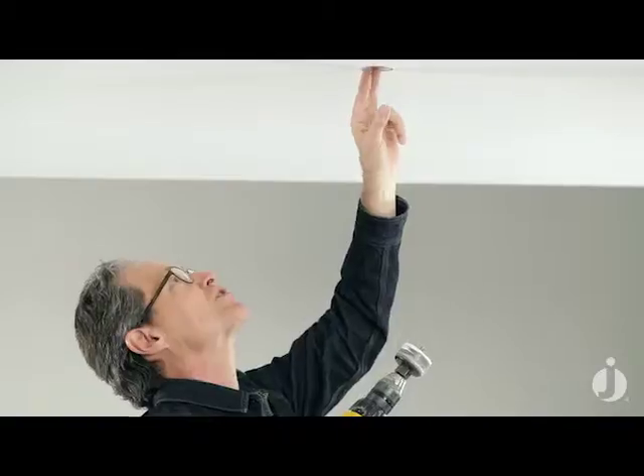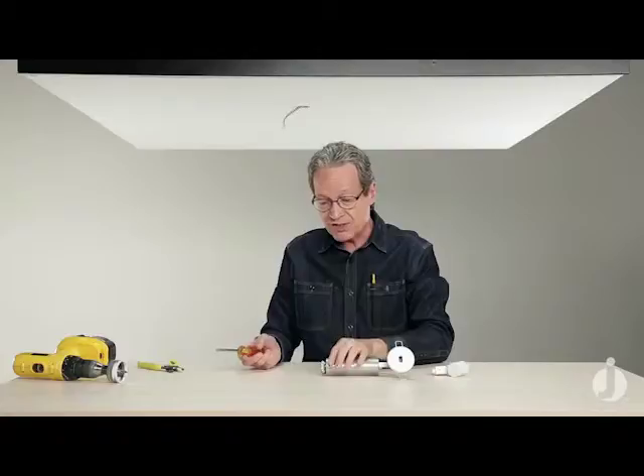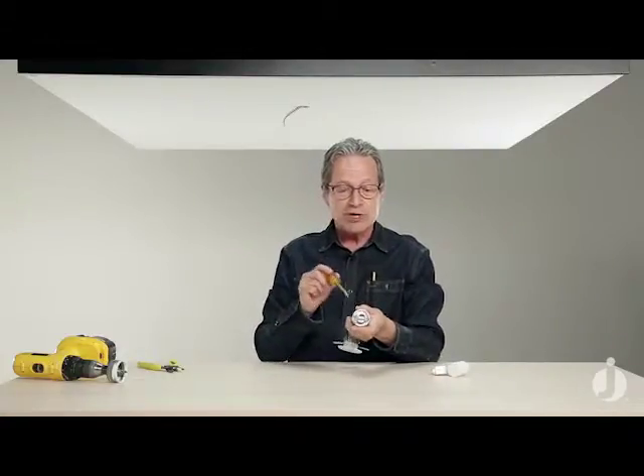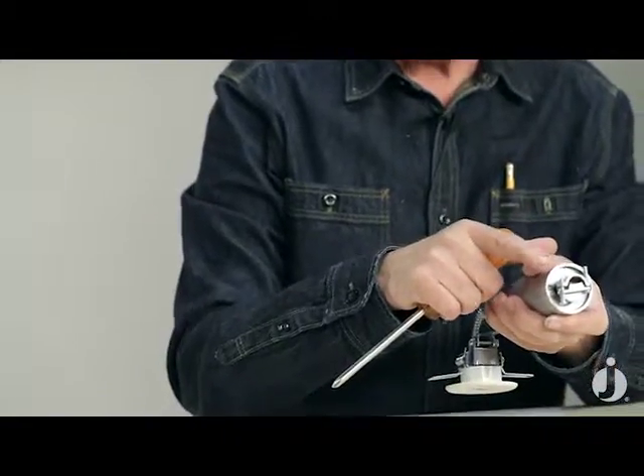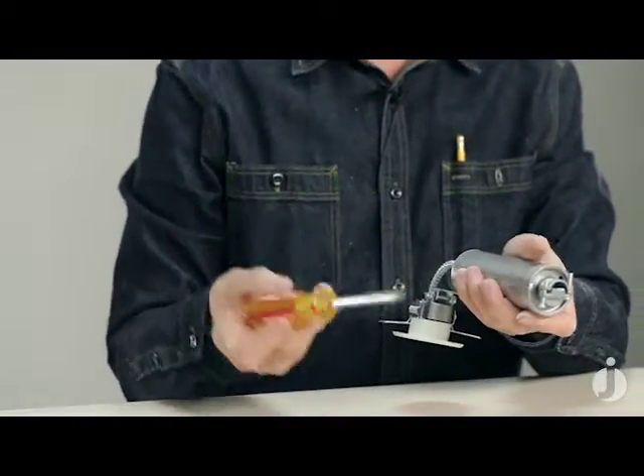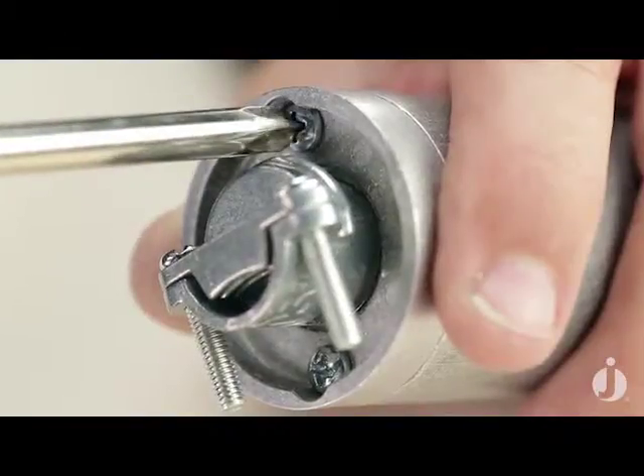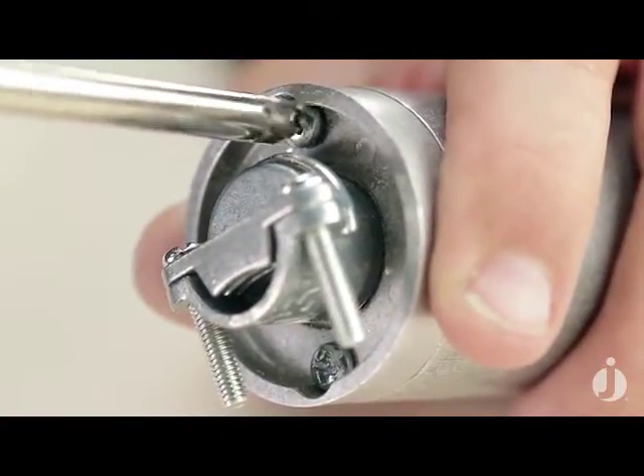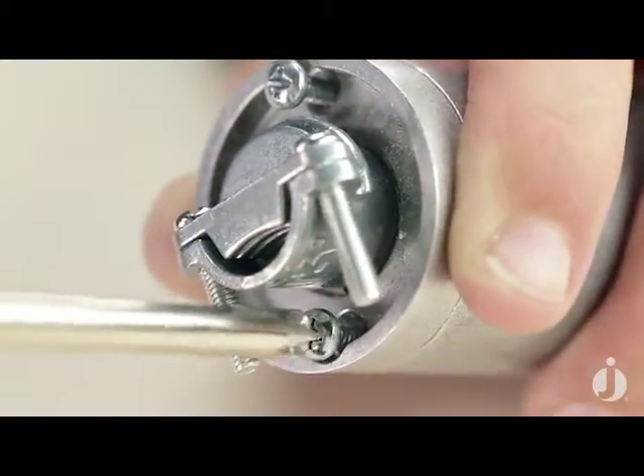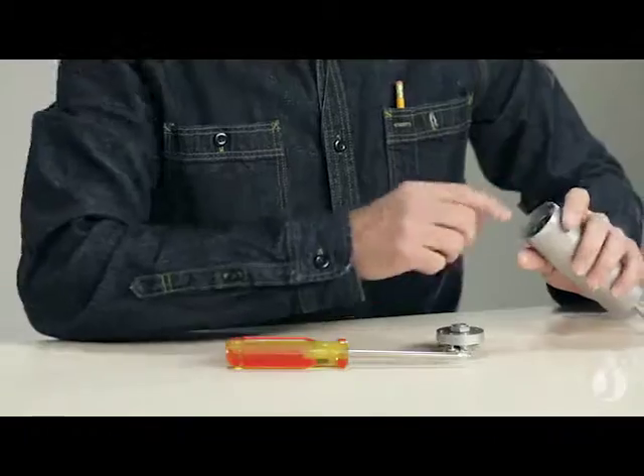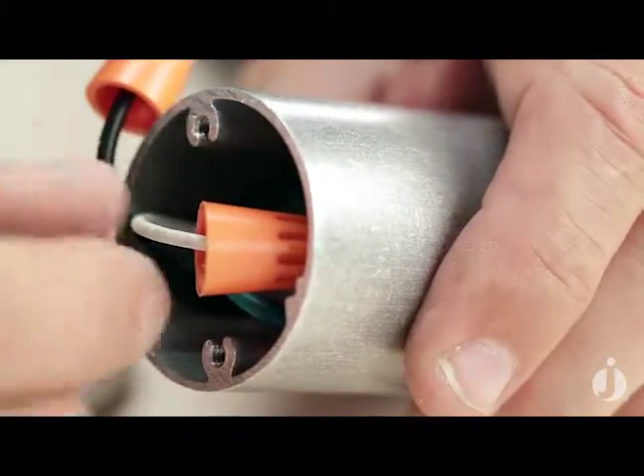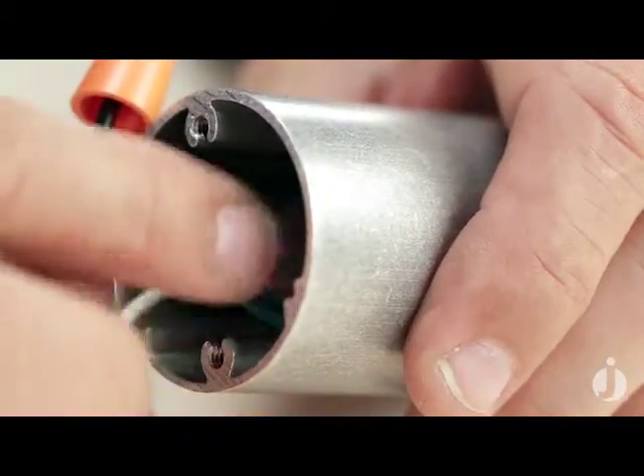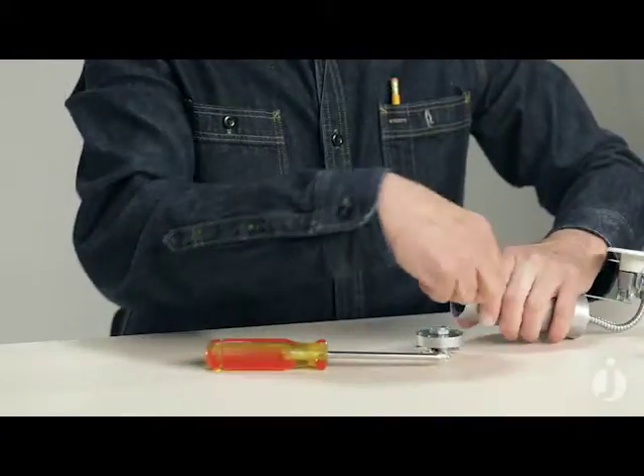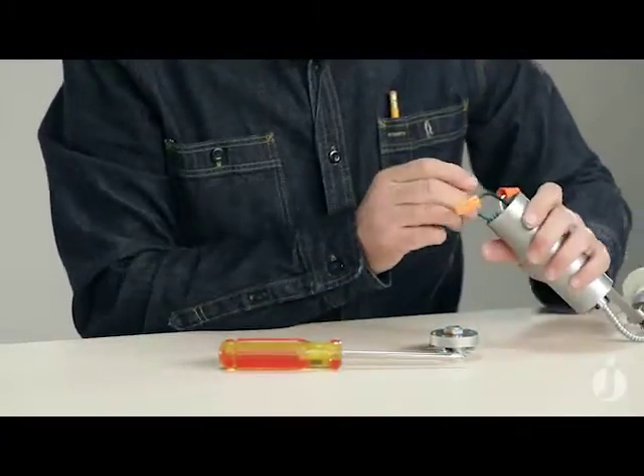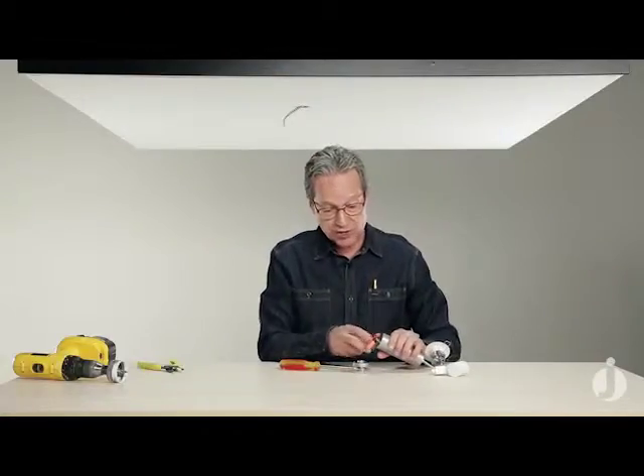So let's pull our wire through the hole. The next thing that we need to do is actually prep the product for installation. The first thing that I'm going to do is remove that cover that goes over the transformer to expose my wiring compartment. And I need a Phillips screwdriver. I'm going to remove the 2 screws that are holding the wiring compartment cover on. And you can see that inside of that wiring compartment, I have 3 wires, a black hot, a white neutral, a green ground, and in this case, also my electronic transformer.